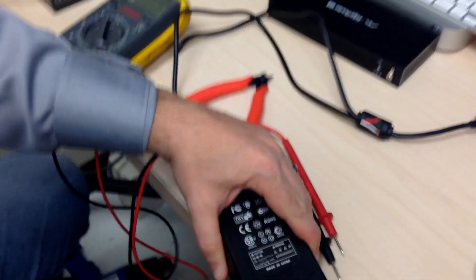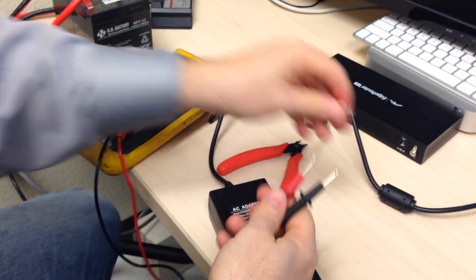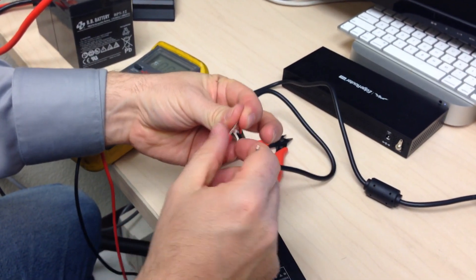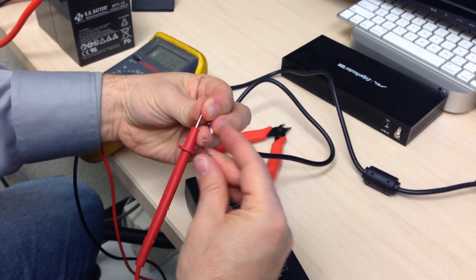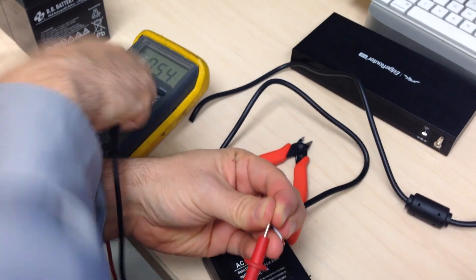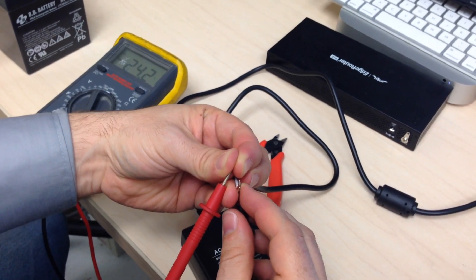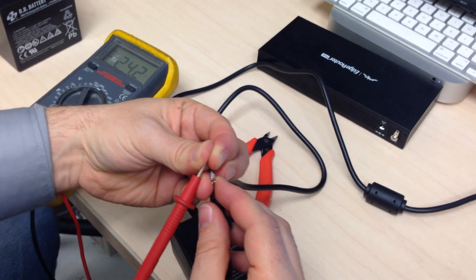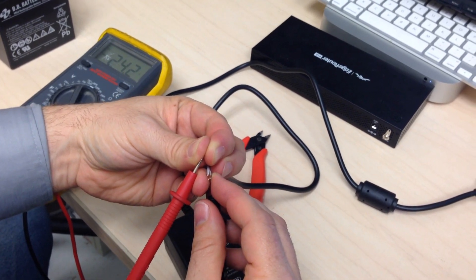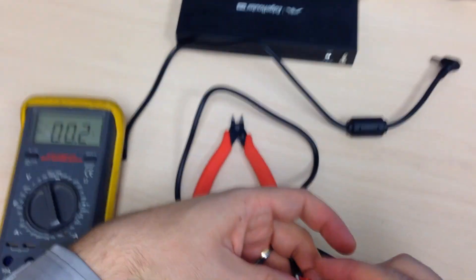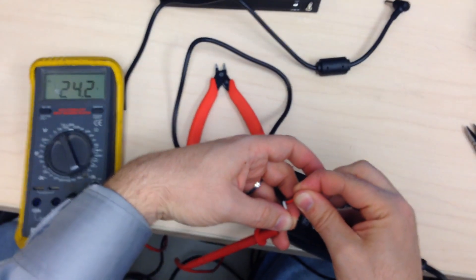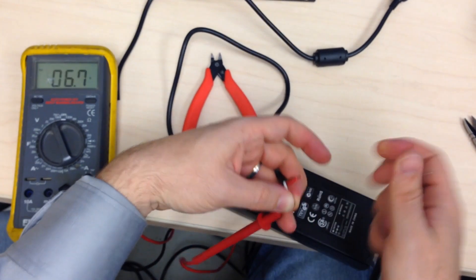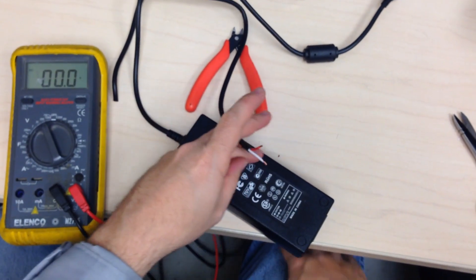Alright, so I set it to 20 volts DC. I'm guessing red is going to be hot, but we'll make sure here. No, I need to set it to 200 volts because it's 24 volts, not 12 volts. And I was wrong. White is positive. So I see how it says negative, it just means I have the leads backwards. So if I switch white... white is positive. 24.2 open circuit. So that is going to probably be regulated pretty tight to 24 volts.